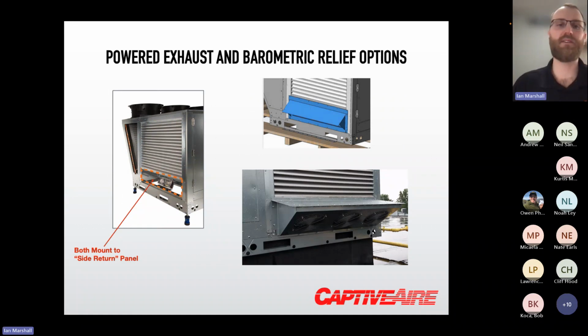So we do have a powered exhaust option and barometric relief. Again, the powered exhaust would be if the unit does have a return. So we have a few different options, and we'll look at it case by case depending on the job. Sometimes a separate exhaust fan makes more sense than trying to get an exhaust through the unit. We have this simple pressure relief exhaust, which is just a set of a few ECM fans.